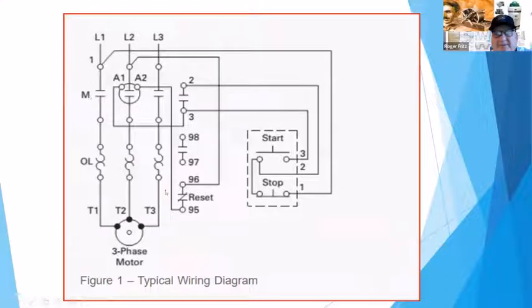Advantage of it was basically simple, but the disadvantage was the inrush current. When a motor started across the line like that, because it wasn't creating its counter EMF back to the line, you would get anywhere from 4 to 6 times the running current. So if the motor is rated 100 amps, it would take 400 amps of power to start it, which took a very large generator. Sometimes almost 600 amps, just short term, to get that thing up and rotating.